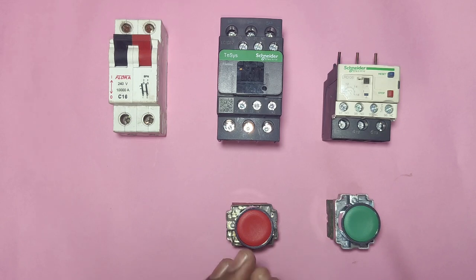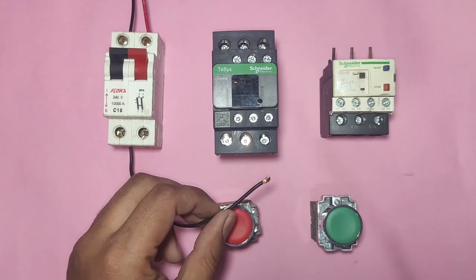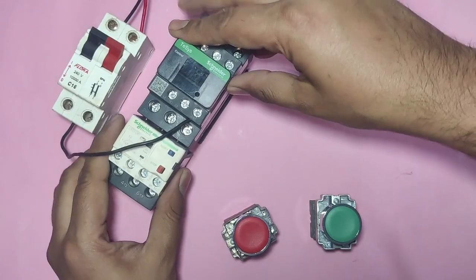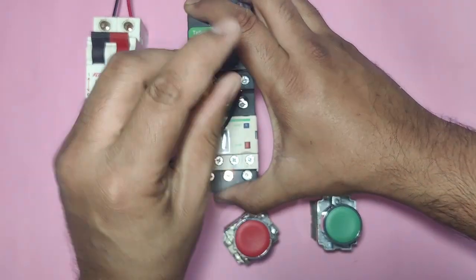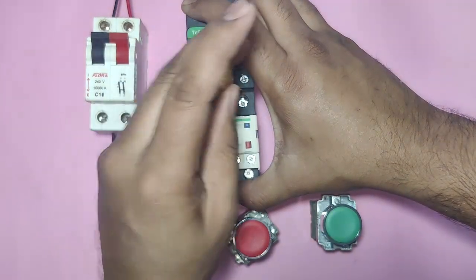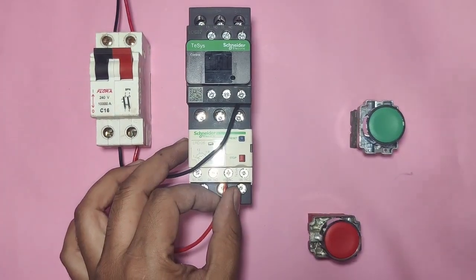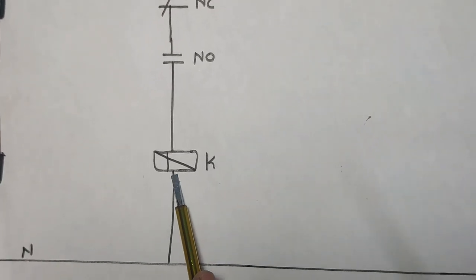For the stop/start buttons, we connect one NC push button and one NO push button. For control wiring, we connect the neutral wire through MCB and give it directly to contactor coil A2. So neutral connects directly first. We connect the contactor — T1, T2, T3 — to the overload relay and make sure all connections are fully tight. For line wiring, we connect one wire to the MCB output and connect it first to overload relay 95 terminal.